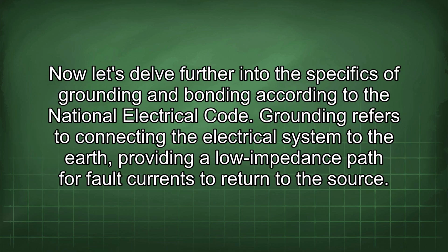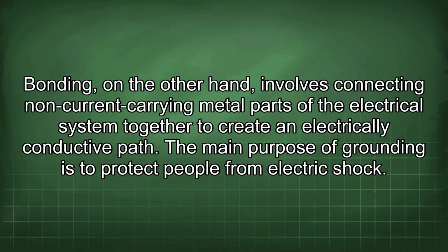Now let's delve further into the specifics of grounding and bonding according to the National Electrical Code. Grounding refers to connecting the electrical system to the earth, providing a low impedance path for fault currents to return to the source. Bonding, on the other hand, involves connecting non-current carrying metal parts of the electrical system together to create an electrically conductive path. The main purpose of grounding is to protect people from electric shock.